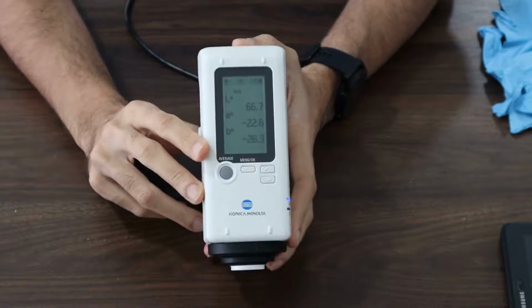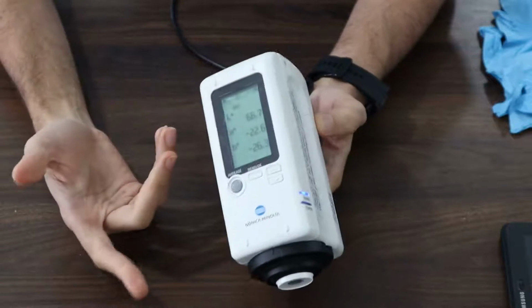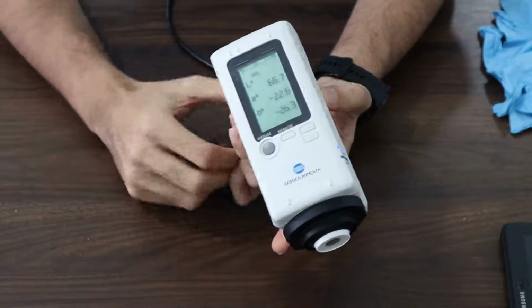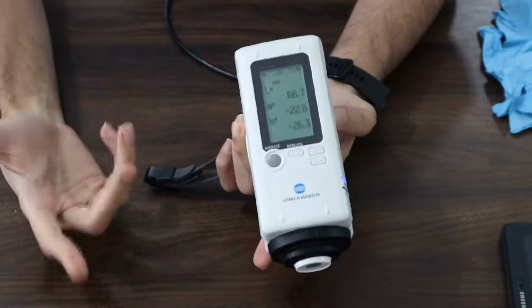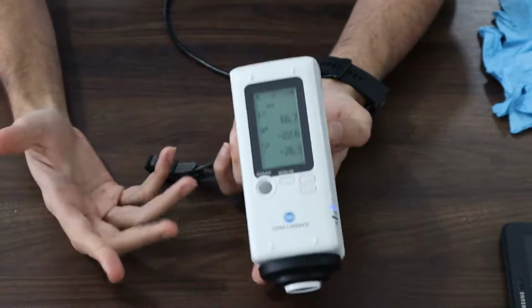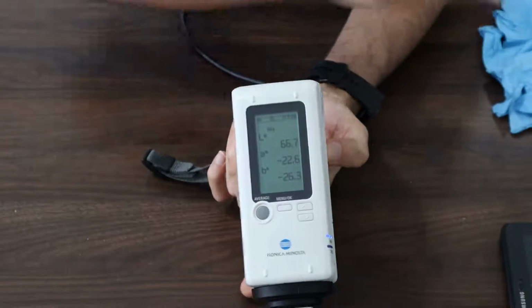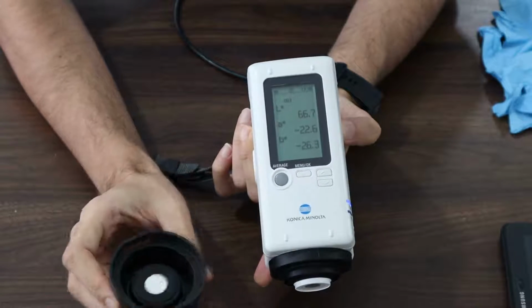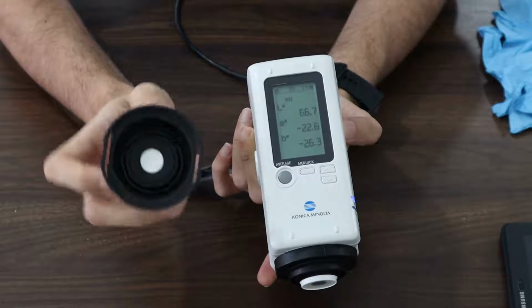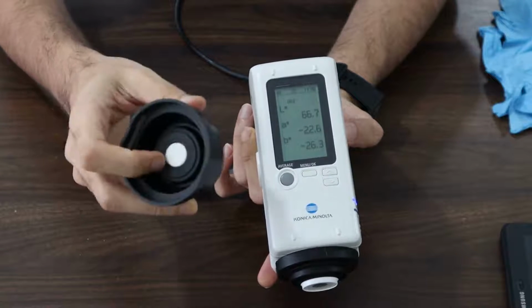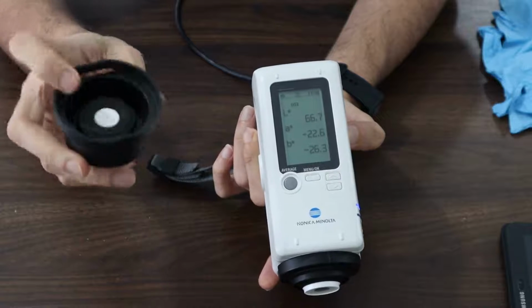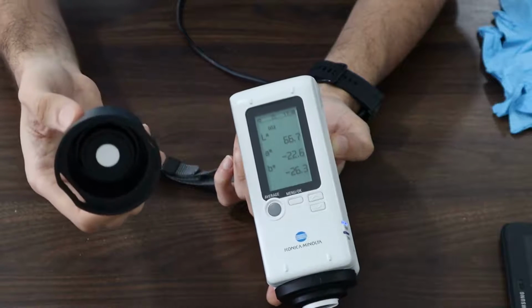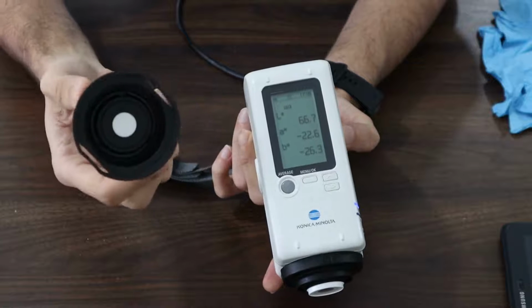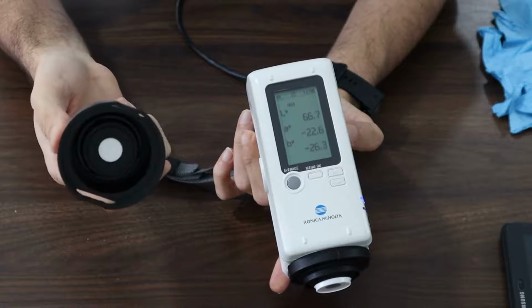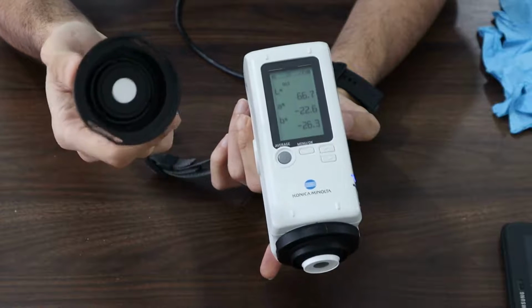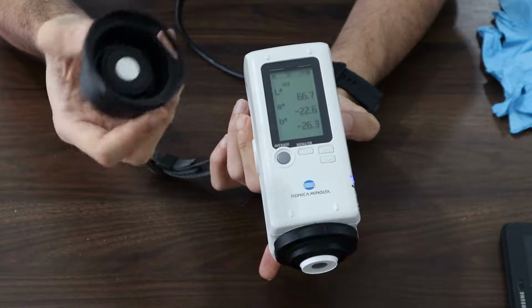As for some maintenance or care, try not to drop the equipment. Though this equipment is handheld and slightly portable, try not to drop it, because dropping it may damage the equipment. Also, for the white calibration plate, once you're done using it, please keep it covered, because any scratch or any dirt accumulated on this may affect the calibration. If it is slightly dirty, you could use a microfiber cloth to clean it. Microfiber cloth is similar to the cloth they give with spectacles or sunglasses. Okay, try not to use tissue paper, because tissue paper is a bit abrasive.